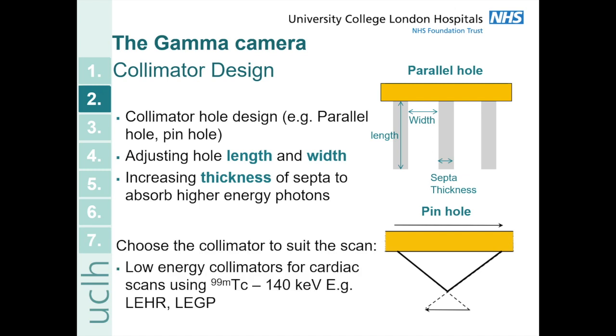You choose the collimator to suit the kind of scan that you're doing. Generally in nuclear medicine we use low energy collimators for cardiac scans because we're using technetium-99m, which is a low energy gamma ray emitter. The collimators we would use would start with LE for low energy and then could either be high resolution HR or general purpose GP.